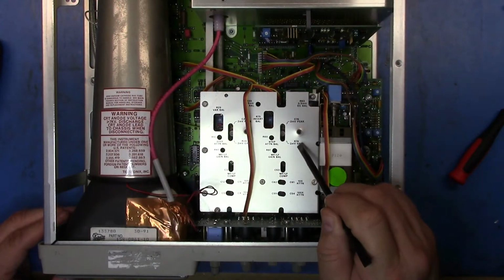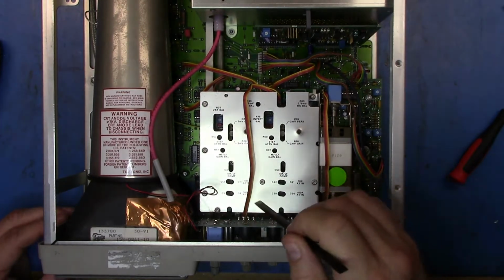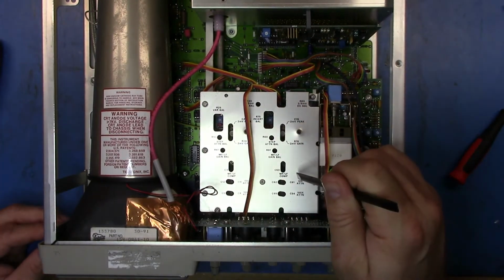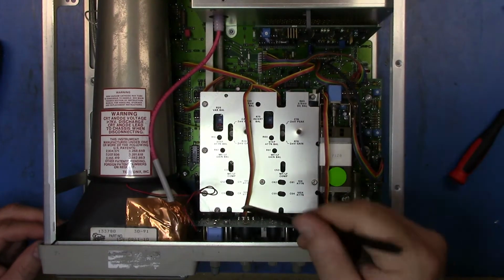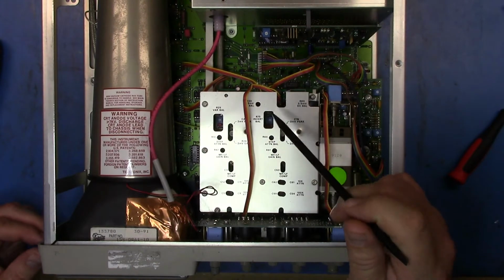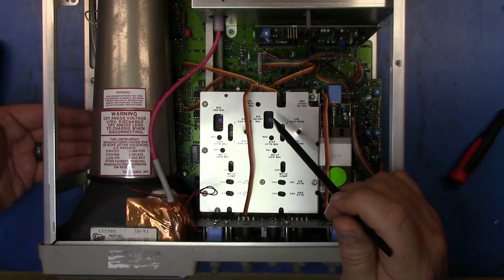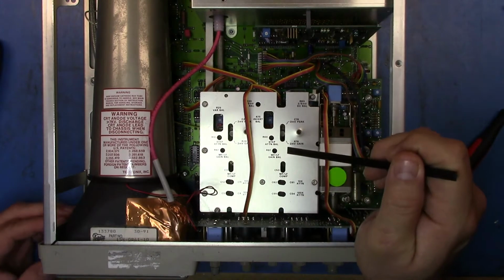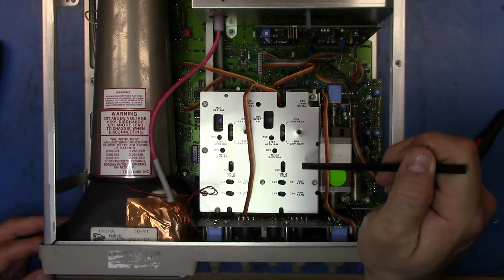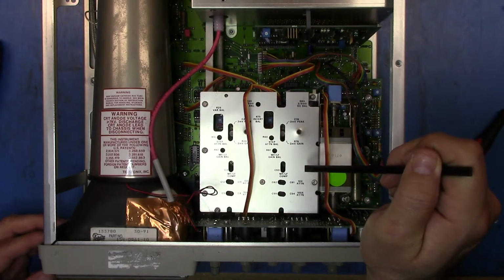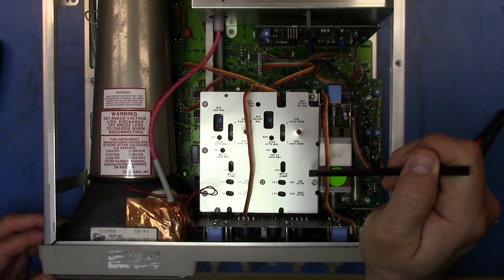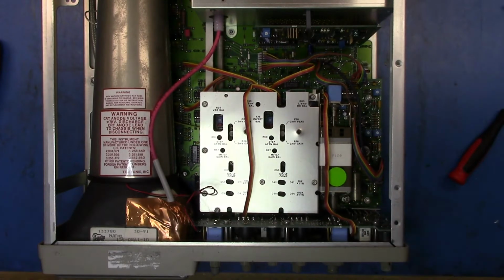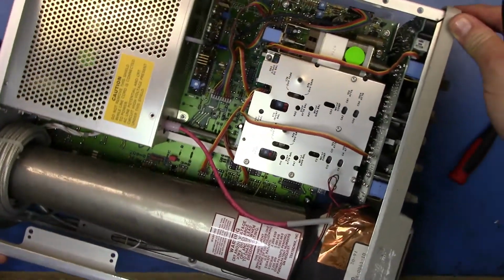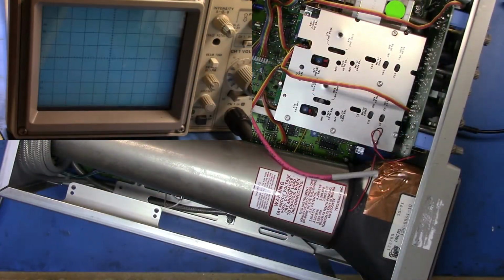So now looking a little closer, we have R26 and R76 over here on the attenuator board, which is this guy here with the switches, then clearly the channel attenuators that were under the cover here. So we're going to change those to get our peak, then we'll use these to set the 2 millivolt gain. And then we should be able to check to see if everything's all hunky-dory. Now let's turn this guy on.